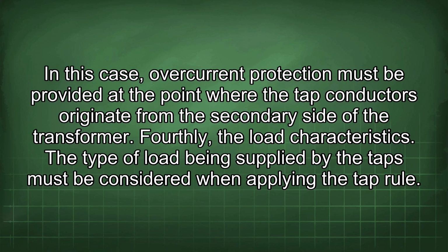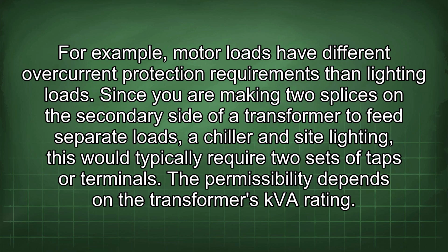Fourthly, the load characteristics. The type of load being supplied by the taps must be considered when applying the tap rule. For example, motor loads have different overcurrent protection requirements than lighting loads. Since you are making two splices on the secondary side of a transformer to feed separate loads, a chiller and site lighting, this would typically require two sets of taps or terminals. The permissibility depends on the transformer's kVA rating.